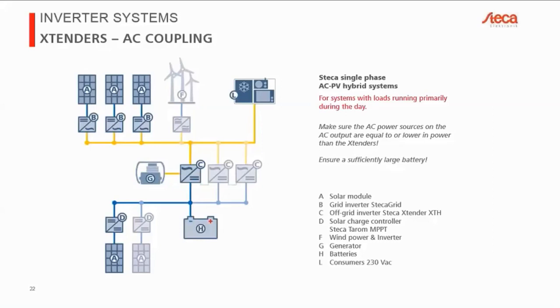Now, all of our grid inverters have what's called a droop mode. This is simply a country code which you select. So you can select Germany, Italy, or droop mode as a country code. And for the droop mode, what happens is exactly that. The Steca grid will react proportionally to the frequency that the extender is providing to it. So let's say if you have 3 kilowatts currently being produced on your grid inverter, but the extender only needs 1.5 kilowatts, it will increase the frequency just enough so that it receives 1.5 kilowatts from the Steca grid.